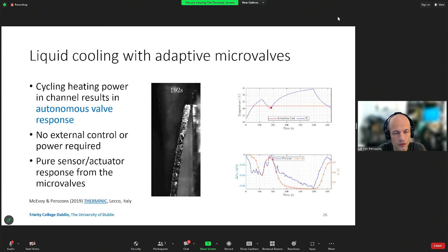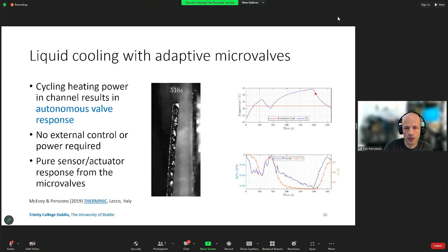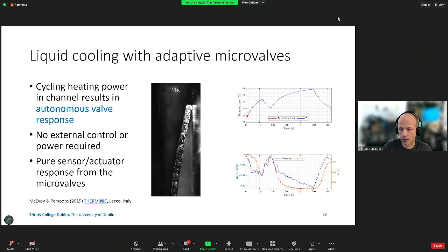There's no external control required here. These things actuate themselves, basically, depending on the temperature that they're sensing. So this could also be an interesting way to deal with non-uniform heat load and also transient heat loads.